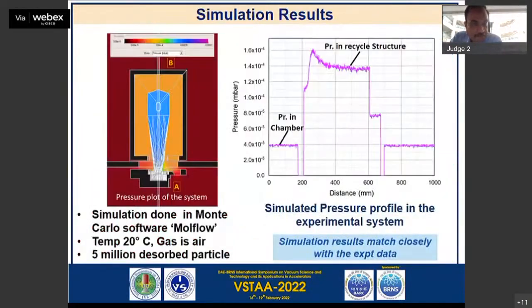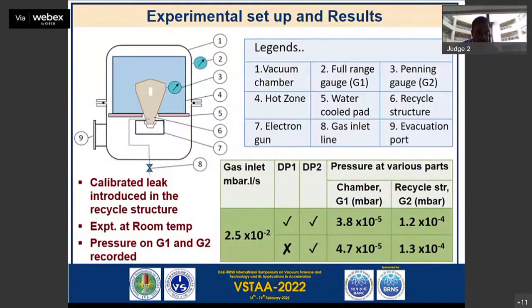So at a 2.5 x 10^-2 leak rate, what I'm seeing is that the chamber pressure, what we actually measure in any process, is 3.8 x 10^-5. And the recycle structure pressure becomes 1.2 x 10^-4. So the difference is more than 3 times. A substantial difference which actually was unnoticed.